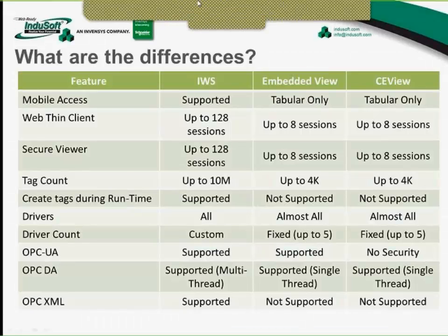Again, on the features, mobile access is fully supported by InduSoft Web Studio, and it's not supported today by embedded view and CE view. Actually, embedded view and CE view only support the tabular version of the mobile access, so it doesn't support everything. And the web thin client is actually supported by all of the platforms, but when you go to embedded view or CE view, you are limited on the number of sessions that you can actually have there. Secure viewers, that's the same thing. So up to 128 on InduSoft Web Studio and up to 8 sessions.